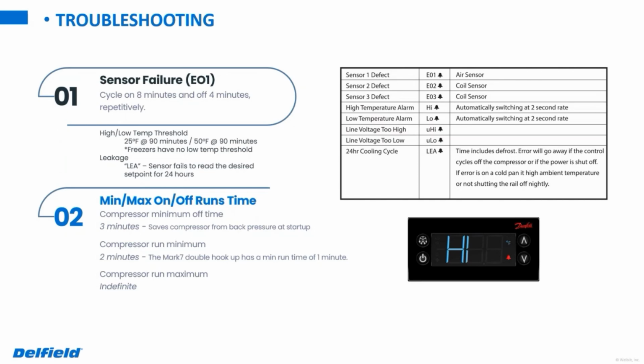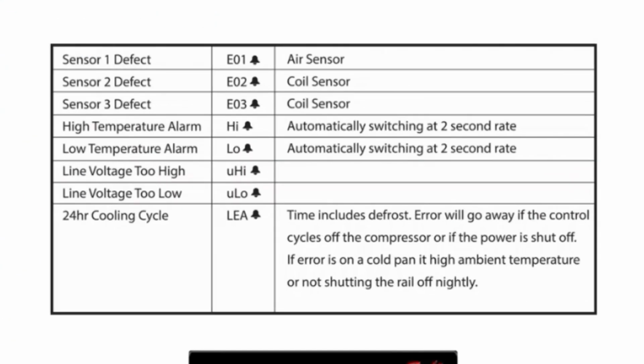As far as troubleshooting goes, you'll notice on the top right we've got a chart that shows the different codes that will pop up on these. The big ones are those probe errors, those sensor errors on the top, the E01, 02, and 03. Typically, when those errors appear for the probes, we're just going to have you replace the corresponding probe, depending on how difficult it is to get into the unit, or if it's something that's maybe under warranty. We might have you replace all the probes to avoid a potential return trip at some point. So if you have one probe bad, a lot of times we'll just have you replace both, on the off chance that we have a problem with the other one in the near future.